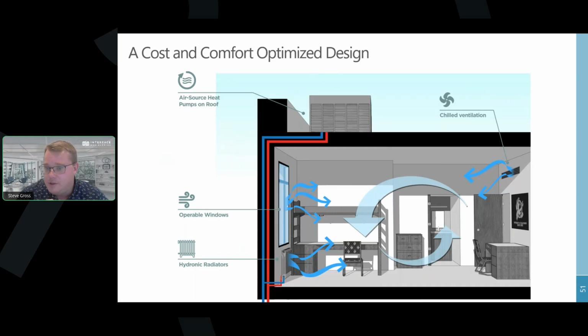On the partial radiant cooling approach, this diagram is actually not quite right. It's there visually to show piping of cold and hot water, but in reality it's a switchover system. So for the month of September, instead of directing hot water to the radiators, we direct cold water and only make chilled water available. We're not adding additional valving, controls, or piping. We're using the same infrastructure that would have been there for the heating-only design and switching it over to partial cooling. The only additional cost is a slightly different type of heat pump that can do both hot and chilled water.